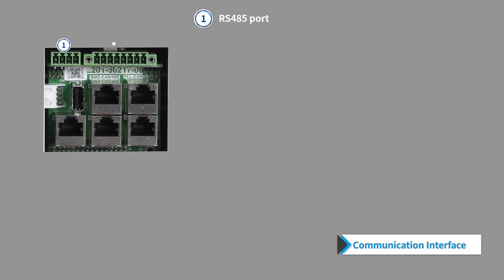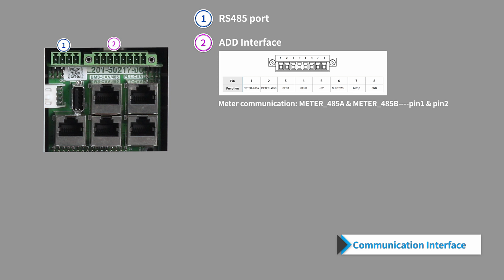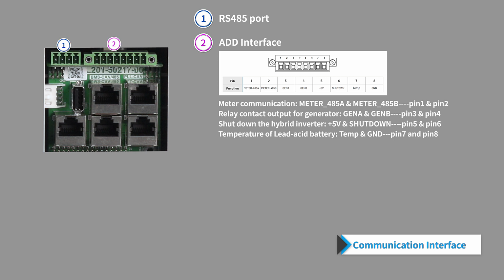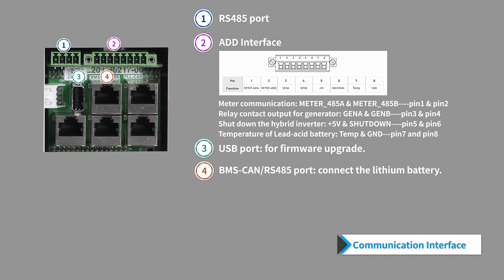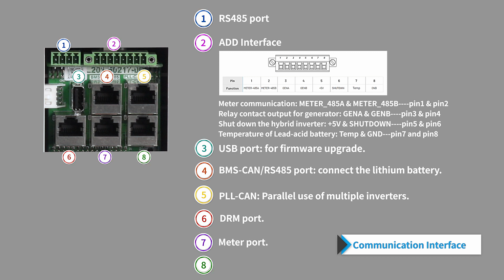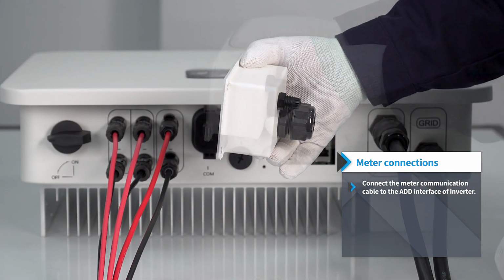1. RS485 port. 2. Add interface, meter communication: meter_485A, meter_485B, pin 1, pin 2. Relay contact output for generator: GENA, GENB, pin 3, pin 4. Shut down the hybrid inverter plus 5V shutdown: pin 5, pin 6. Temperature of lead acid battery: temp, GND, pin 7 and pin 8. 3. USB port for firmware upgrade. 4. BMS CAN RS485 port, connect the lithium battery. 5. PLL CAN, parallel use of multiple inverters. 6. DRM port. 7. Meter port. 8. PLL CAN, parallel use of multiple inverters. The meter connections: connect the meter communication cable to the add interface of inverter.